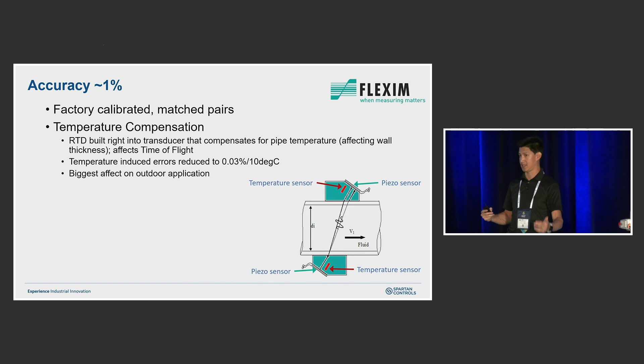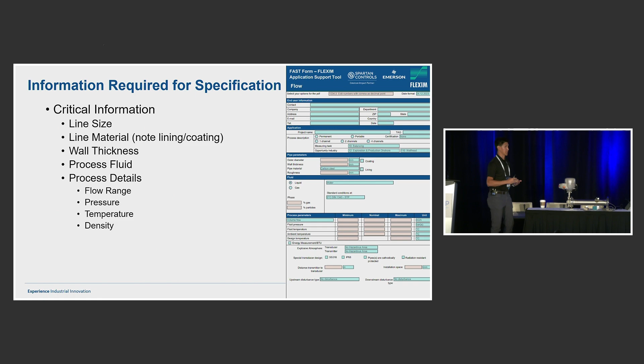This is a bit of an eye chart. Basically, the main information we want to collect to understand whether this is a good fit is line size, line material, pipe thickness, and basically a bunch of your process details. The more you can give us, the better. Other things here can be beneficial too, like understanding what power you have available and what your piping disturbances upstream and downstream are. Those are nice to have, but at the end of the day, to spec one out and understand what accuracy we can get and whether it'll work for the application, those are the key details.